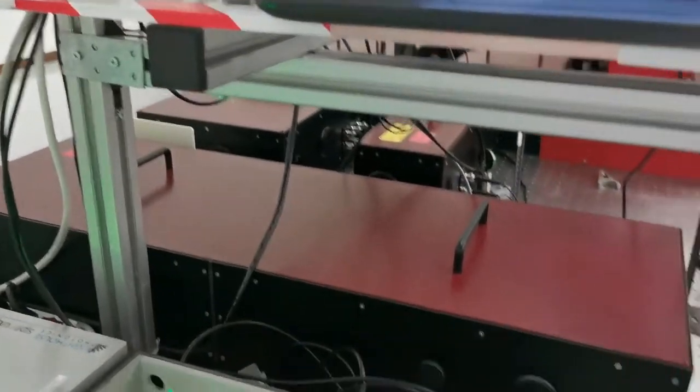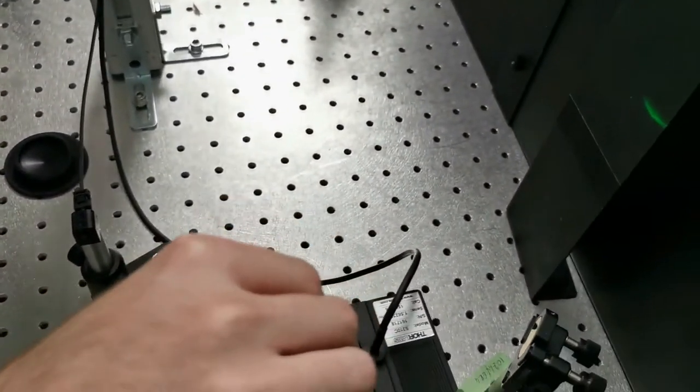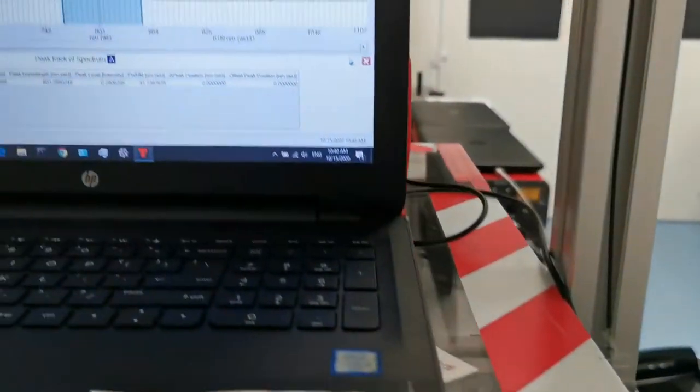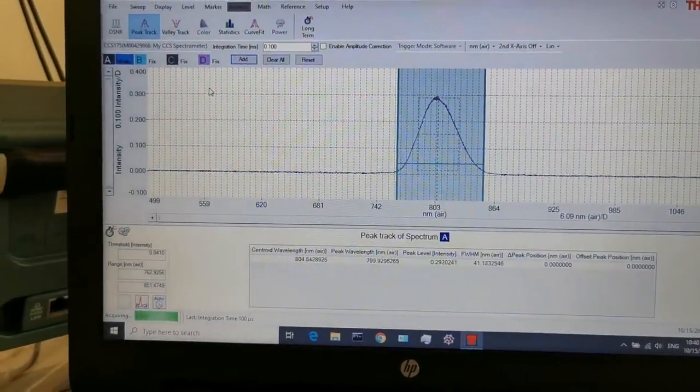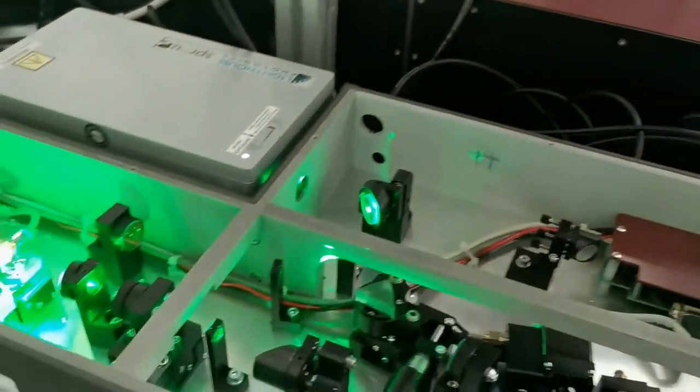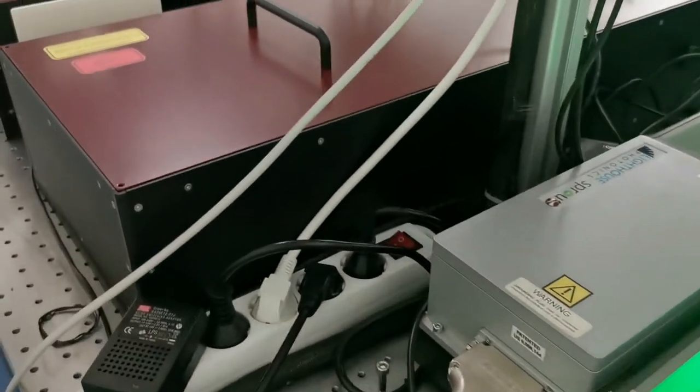The femtosecond oscillator is based on Kerr lens self-mode locking. Under the optimal alignment, the laser oscillator is able to generate ultra-short pulses at 800 nm with approximately 4 nJ pulse energy, 90 MHz repetition rate and about 50 nm spectral bandwidth, which corresponds to less than 20 femtoseconds pulse duration.